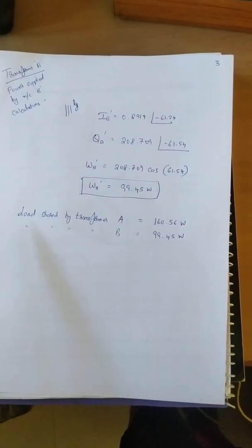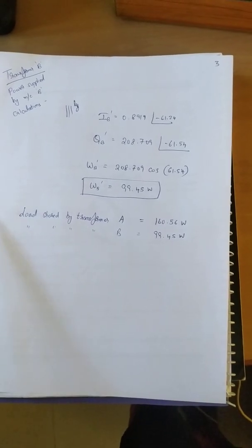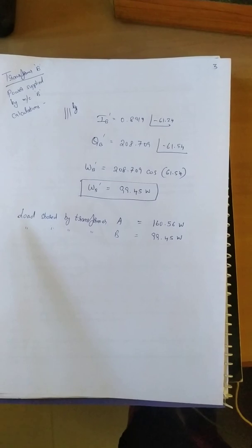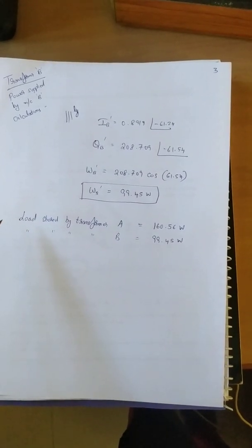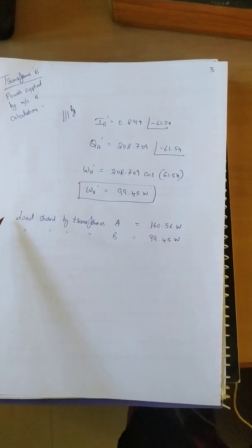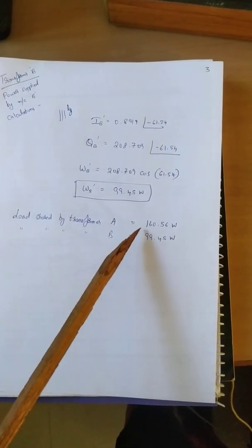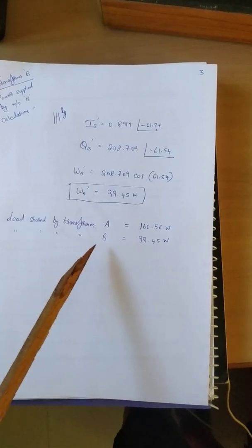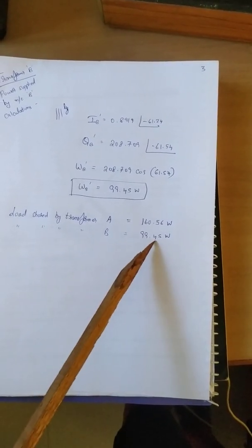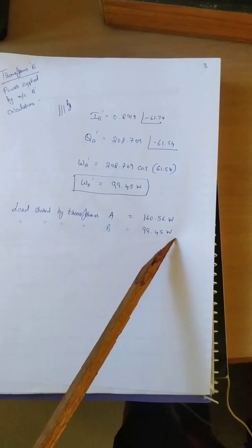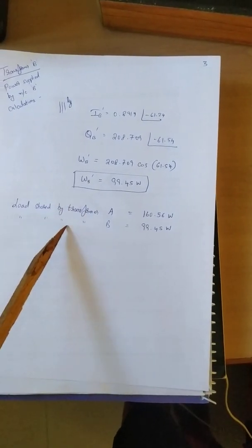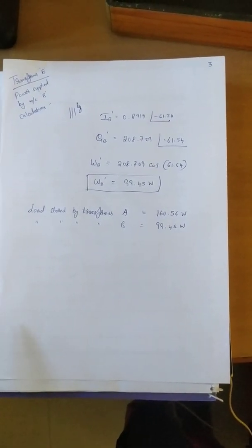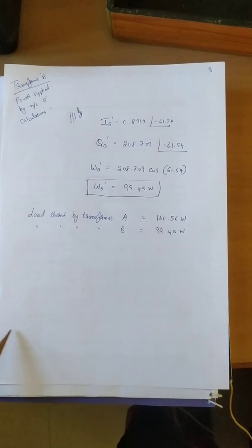After doing these calculations we come to a conclusion that for this particular load, for the current of 2 amperes which is the specimen that we have selected for this calculation, load shared by the first transformer of 2 kVA rating is 160.56 watts and load shared by second transformer of 1 kVA rating is 99.45 watts. Similarly, load shared by Transformer A and Transformer B for all the readings have to be calculated. This finishes the calculation specimen calculations for this experiment.